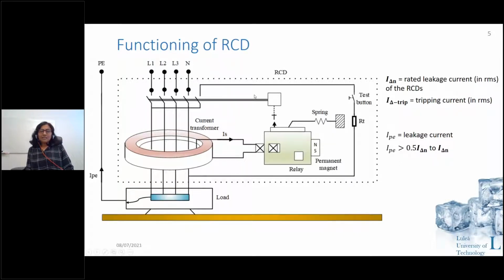And when I said that DC currents often lead to blinding of RCDs, it is because the RCD has mainly a CT, a current transformer, which can get saturated due to the presence of DC currents. But in today's presentation, I'll not be talking about pure DC current, although we have worked with pure DC current as well. I'll be presenting more of what we found in our results with quasi-DC, supraharmonics, and harmonics. So how do they affect the operation of an RCD? Because it's not as straightforward as DC. I don't know if it really generates saturation or how it impacts. That is the reason why we did the study.